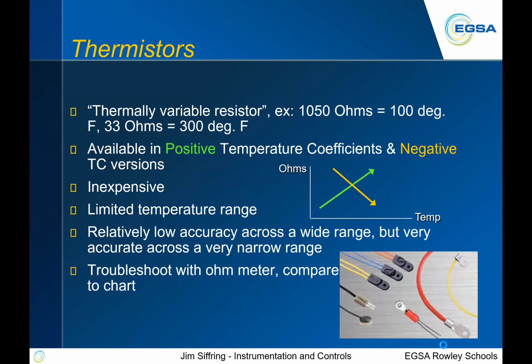Thermistors, a thermally variable resistor, are very similar to an RTD, but different in a few ways. It's a simpler device. They typically have a lower range, things like that, and are much less expensive. They're available as a positive and negative coefficient, so it may be that resistance goes up as temperature goes up, or it may be that resistance goes down as temperature goes up. But they're cheap, they're pretty easy to install, all that kind of stuff. Typically it's a less expensive way to measure temperature.